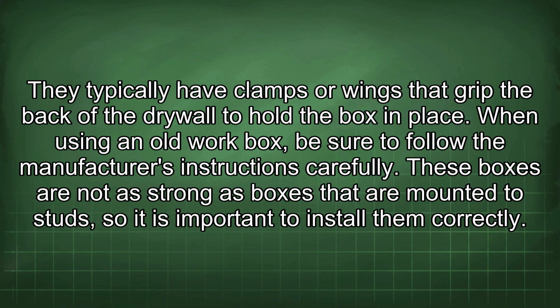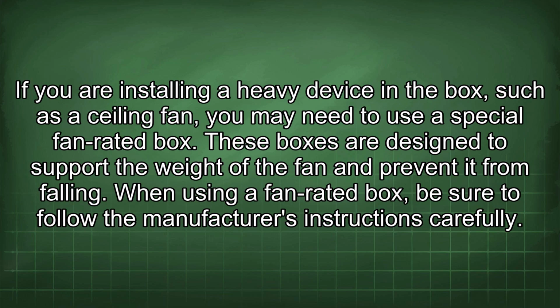When using an old work box, follow the manufacturer's instructions carefully. These boxes are not as strong as boxes mounted to studs, so it is important to install them correctly. If installing a heavy device in the box, such as a ceiling fan, you may need to use a special fan-rated box.